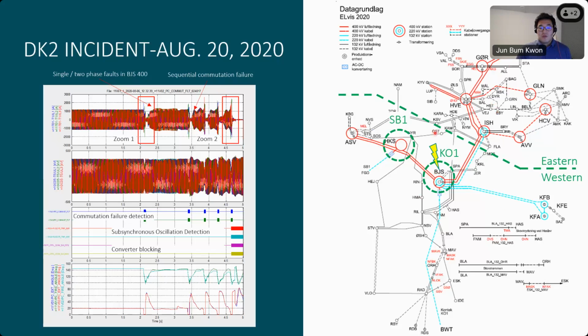So all the consumption in the DK2 power system was basically covered by these two HVDCs and some renewable energy from wind and PV, but not much. Once the incident happened that decoupled the western and eastern part of Zealand, we experienced multiple sequential events — quite complicated to explain in detail — but basically we had multiple commutation failures, which led to the trip of the Storebælt HVDC and the synchronous condensers at the stations.